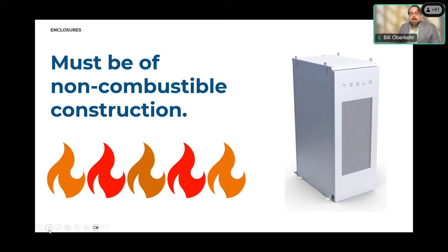Electrical disconnects are extremely important to first responders, and they should be in a secure location with signage to direct the fire department to the proper place. Even though you may shut down the energy storage system, the stored energy inside the batteries does not dissipate. That is a key point to bring to first responders. This one device can shut down all cabinets or containers that are at the site. Firefighters should be advised to be careful when shutting this system down when there are no signs of fire.